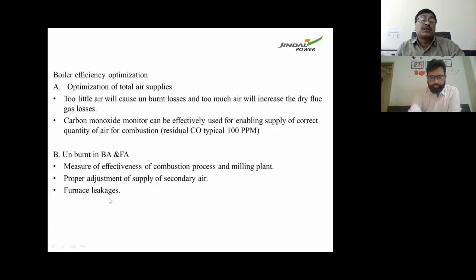How can we optimize the boiler efficiency? First of all, we should consider the total air supply. Too little air will cause unburnt losses. Too much air will increase the dry flue gas loss. Carbon monoxide should be monitored closely for enabling supply of the correct quantity of air for combustion. Similarly, unburnt in fly and bottom ash should be measured regularly, as a measure of effectiveness of the combustion process and milling plant, with proper adjustment of the supply of secondary air to reduce the fly ash and bottom ash unburnt. Furnace leakages should be monitored.